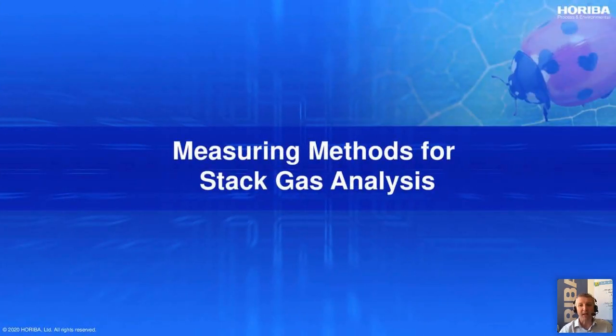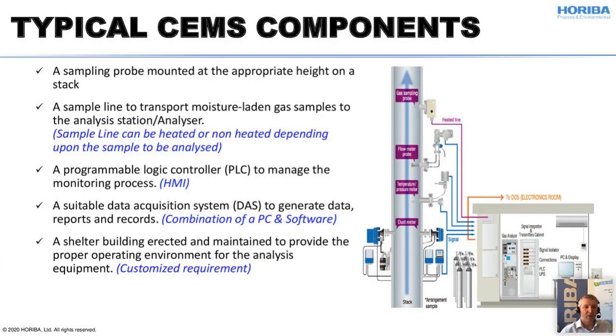First part here are the different methods to bring the gases from the stack or gas duct to the analyzer module. What are the typical CEMS components? You can see here the stack where the gas is coming from the industry, from the pollutant, and brings the gas to the ambient air. A sampling probe is mounted at the appropriate height on the stack. Next one is the sample line, which needs to transport the gas from the stack to the instrument. At the instrument or in the cabinet, a programmable logic controller, short PLC, or also a human-machine interface, HMI, is installed to manage the monitoring process and also to connect the people to the system.